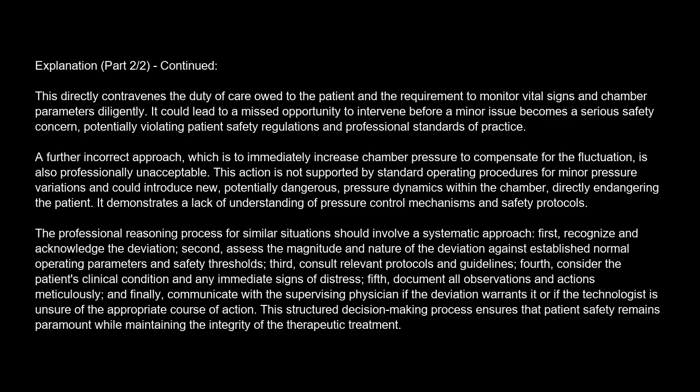A further incorrect approach, which is to immediately increase chamber pressure to compensate for the fluctuation, is also professionally unacceptable. This action is not supported by standard operating procedures for minor pressure variations and could introduce new, potentially dangerous pressure dynamics within the chamber, directly endangering the patient. It demonstrates a lack of understanding of pressure control mechanisms and safety protocols.